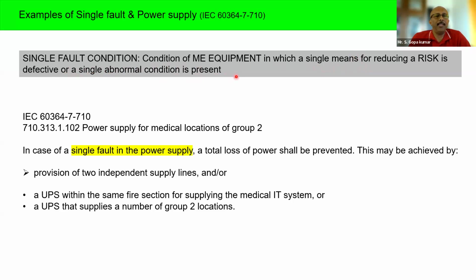This single fault condition can exist in several ways. It can be mechanical, chemical, electrical, or whatever it is. The medical electrical equipment shall be made, installed and maintained in such a way that it is able to deliver the performance it is supposed to during a single fault condition. That means even during a fault condition, the device must operate.